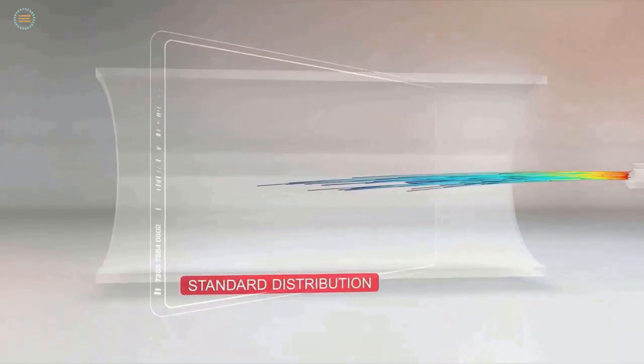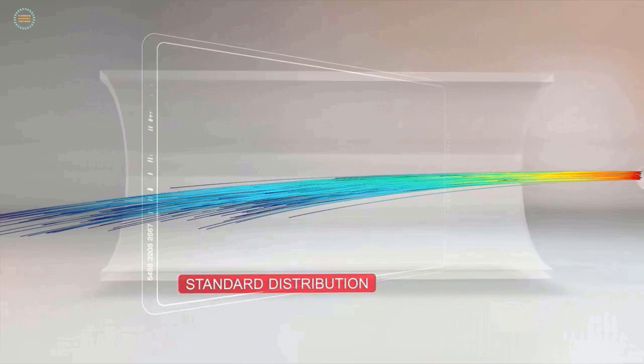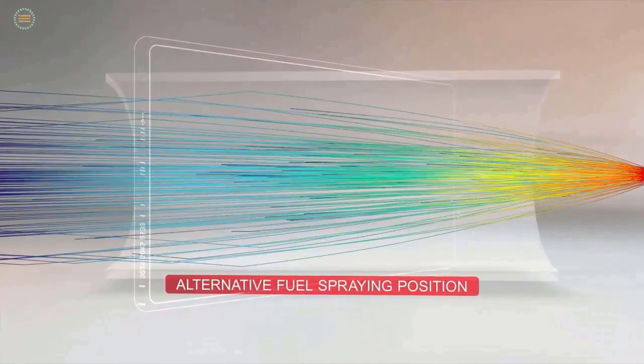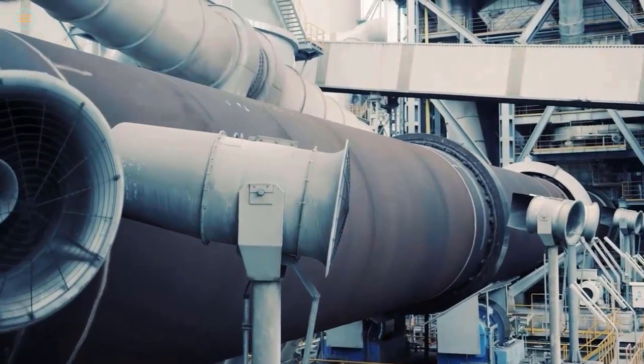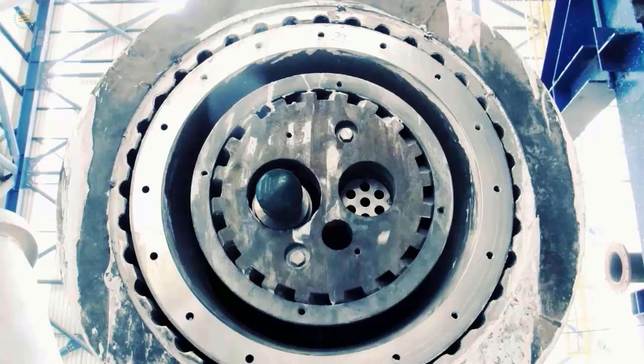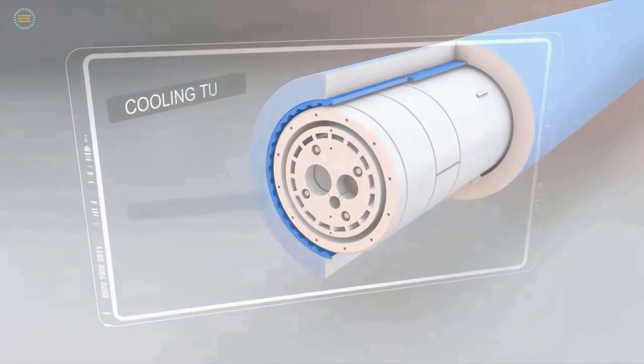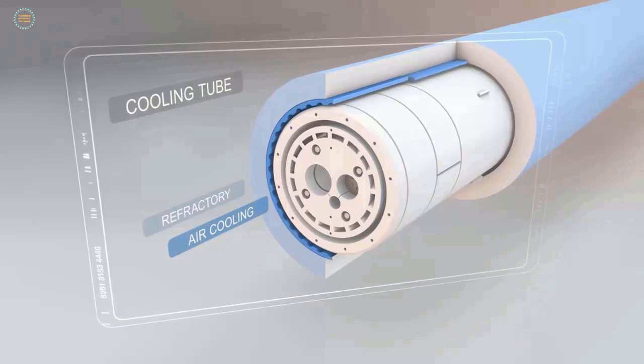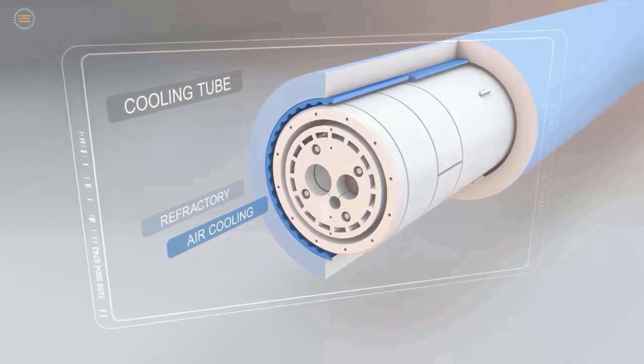The swirl air guarantees fast ignition and efficient combustion of the fuel. Due to the adjustable swirl system, alternative fuels are better distributed in the flame core. The spraying position of the swirl element ensures efficient distribution and complete combustion of the fuel particles. PyroJets are extremely reliable due to their sturdy design. The castable cooling tube is highly resistant against heat and dust in case of refractory failure, giving extra protection for the burner tip. The fins at the cooling tube increase the heat exchange between cooling air and refractory.